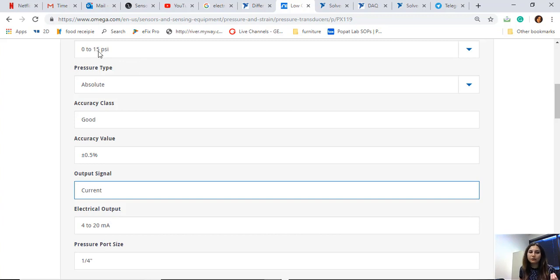So all you have to do is to find the ratio and get the equation out, and then in your LabView program, your data acquisition system is going to measure the signal in terms of current, for this specific instrument, and then you get the current, you know the ratio, a simple math, and then you can transfer that current into a pressure in terms of psi. So it's as simple as it is, and it's always linear. Like all these websites that you purchase a transducer or transmitter from, their ratio is always linear. So that was a current.